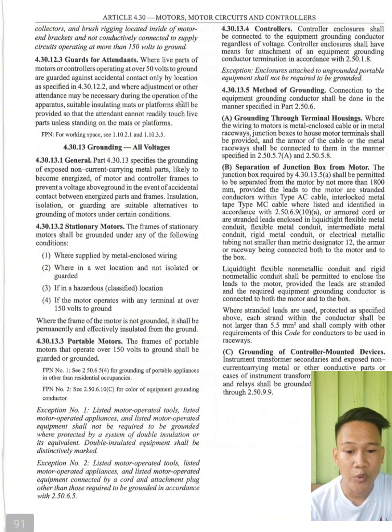Next, we have 4.30.13, Grounding, all voltages. So, 4.30.13.1 In general. This part specifies the grounding of exposed non-current-carrying metal parts likely to become energized, such as motor and controller frames, to prevent a voltage above ground in the event of accidental contact between energized parts and frames. Insulation, isolation, or guarding are suitable alternatives to grounding of motors under certain conditions.